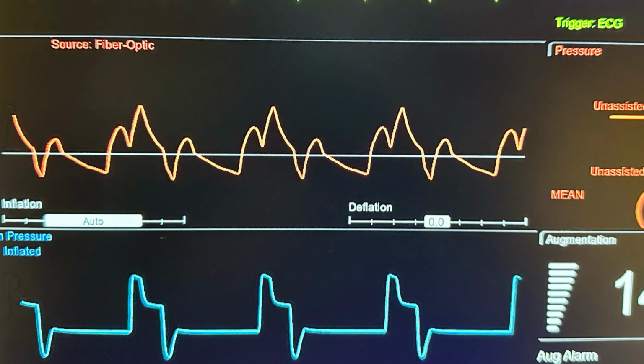Yeah, and one of the things that can be confusing is you look at that diastolic, the assisted diastolic, and you're like, wait a second, 49. That's way lower than it should be. That should be higher. Mm-hmm. And it's because you're measuring two points of that diastolic phase. You're measuring the very maximal impulse, and then when it deflates and it leaves this void, we say it's kind of like a suction effect to offload the LV. That's why it drops down. So you're seeing the beginning of the diastolic period and the end of the diastolic period.